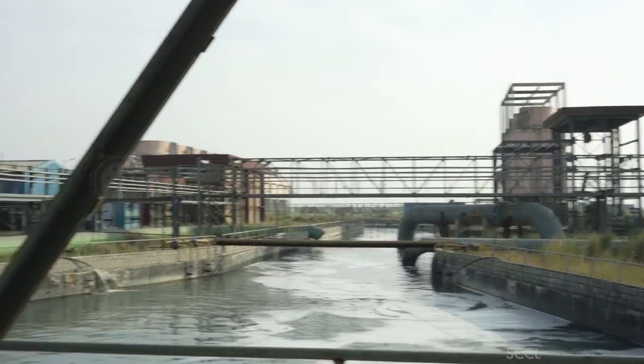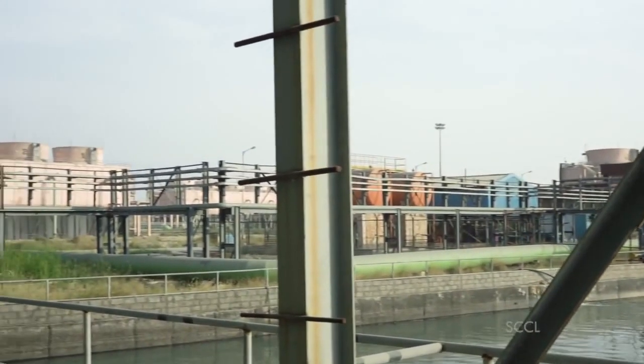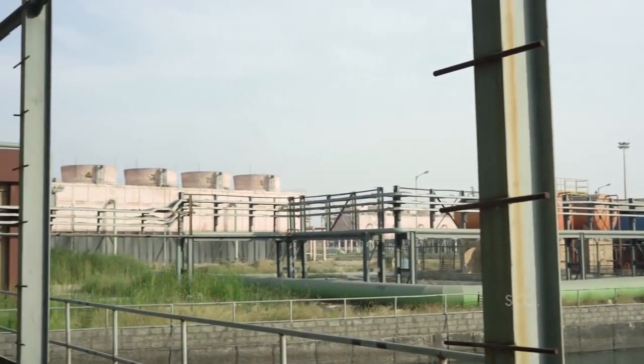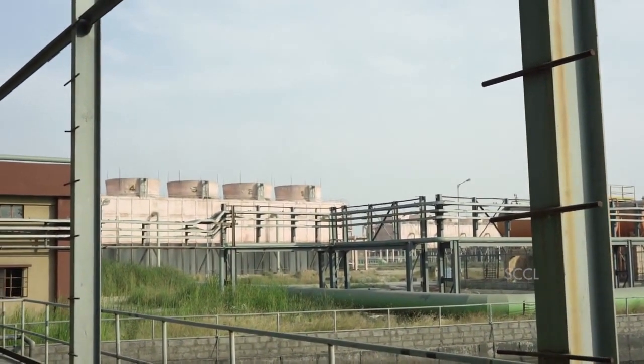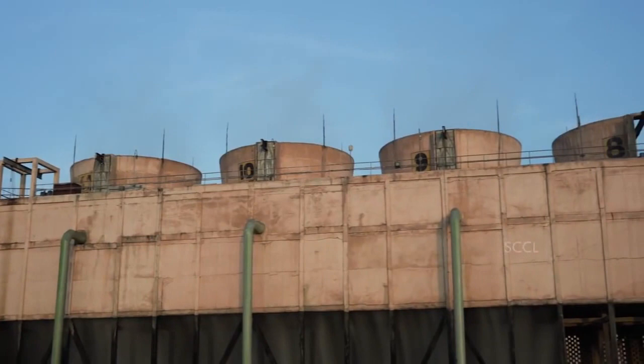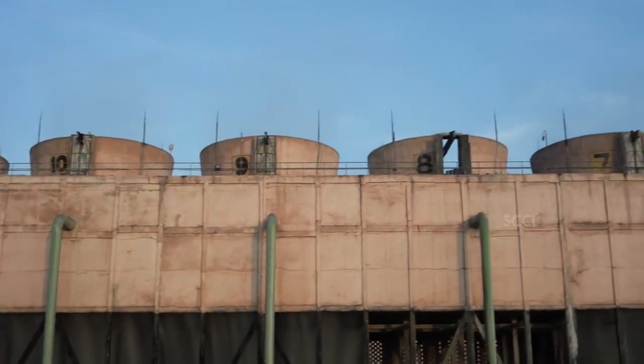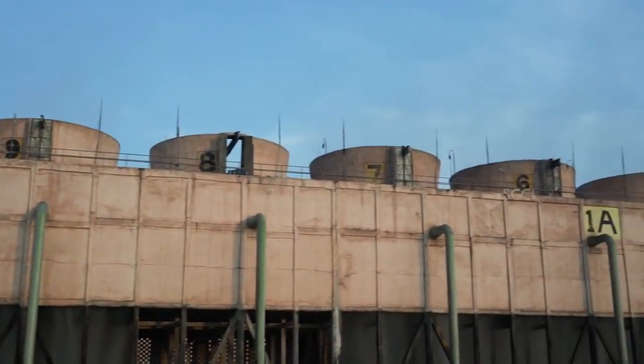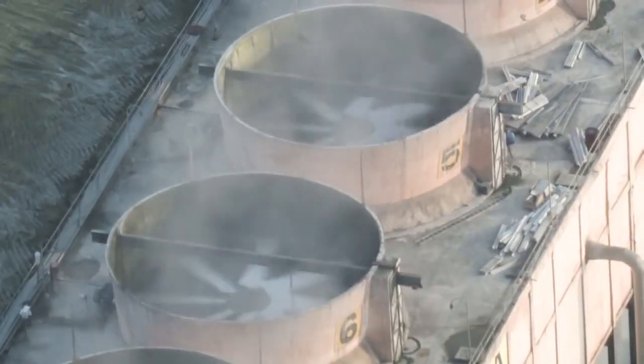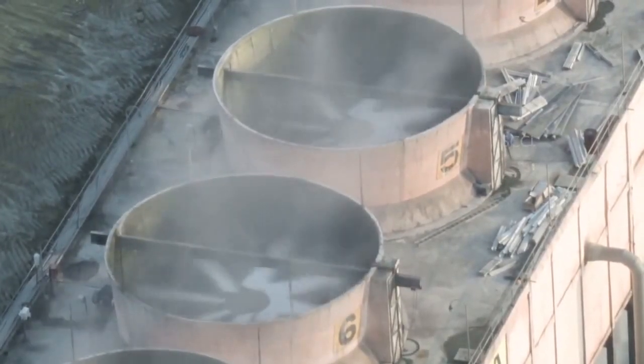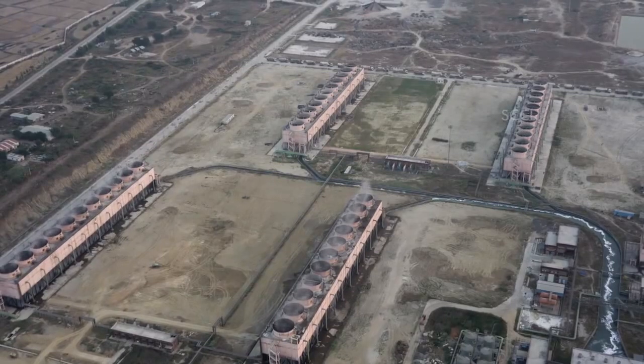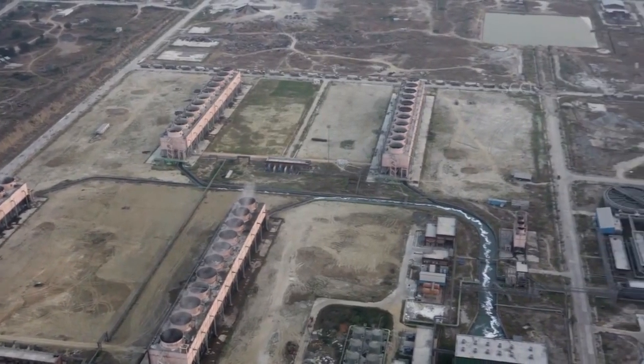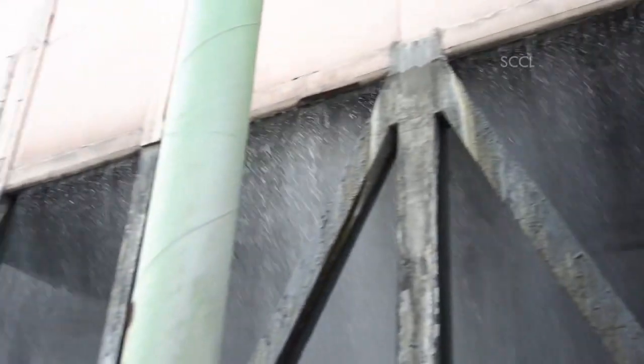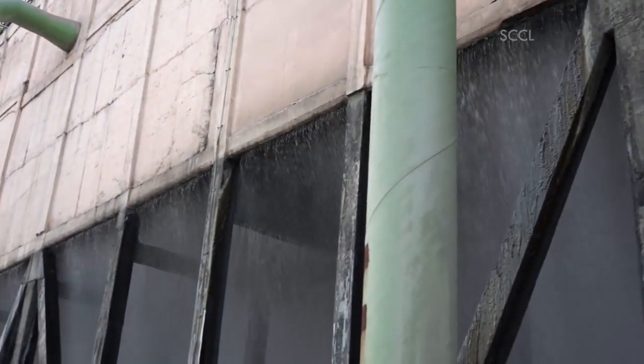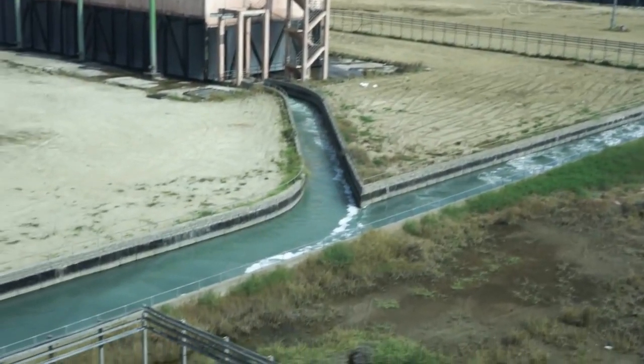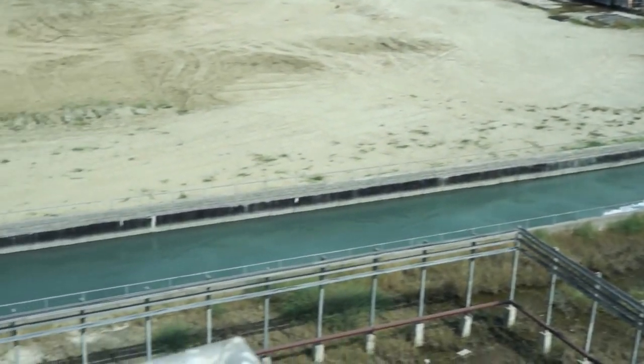As steam condenses, the chilled water inside the condenser pipes becomes warm from the heat of the steam, so it is sent to a cooling tower. At STPP, induced draft cooling towers are constantly at work, where cooling is done by mechanical fans. There are 44 fans, out of which at least 40 fans will be working throughout the day. The freshly chilled water returns to the condenser to repeat the process of cooling more steam.